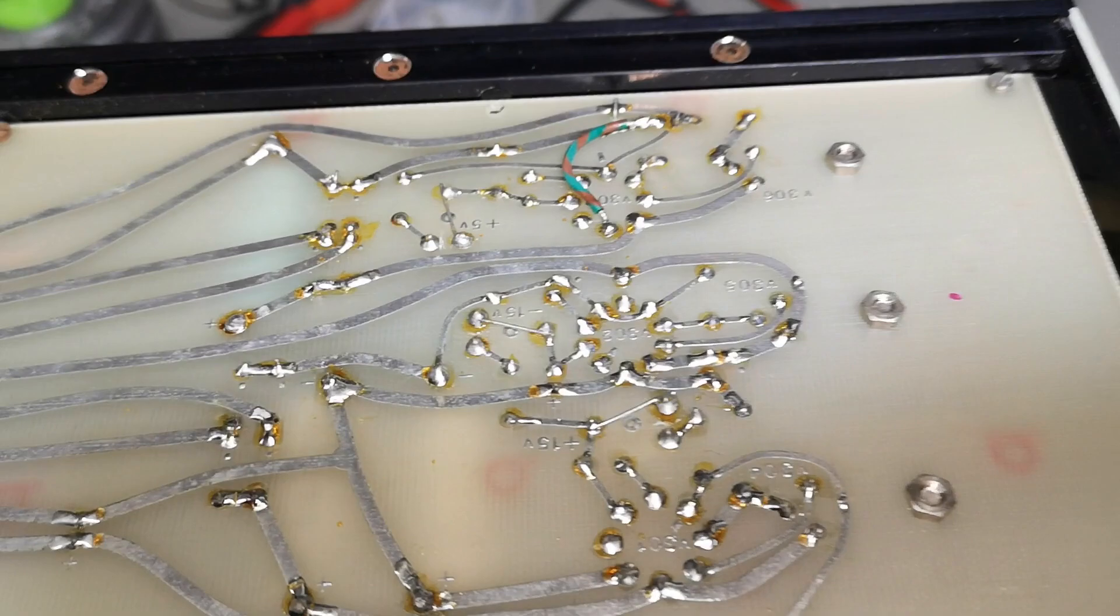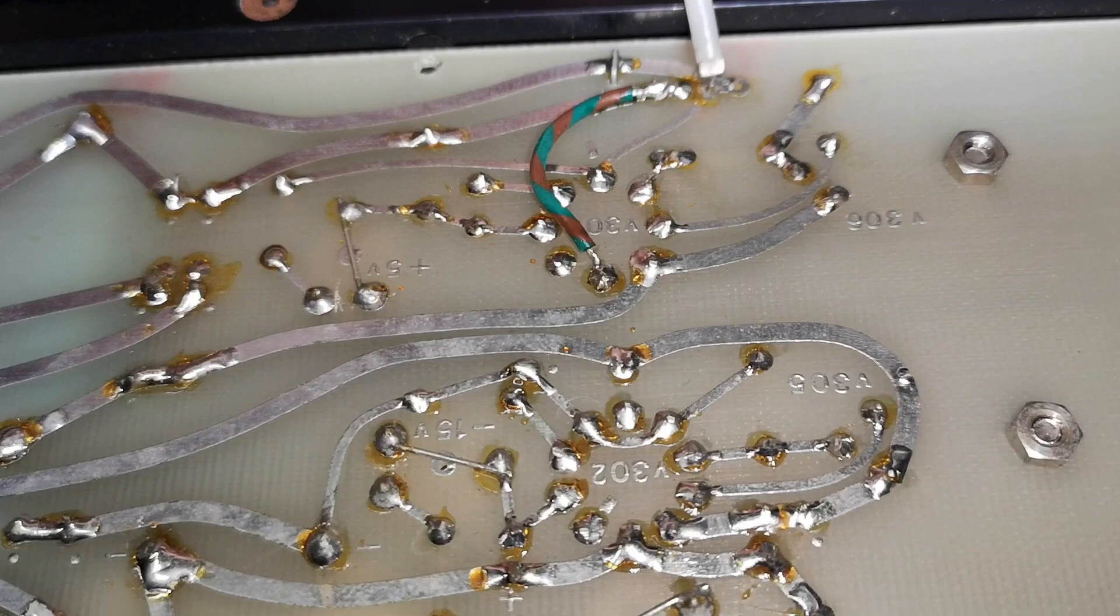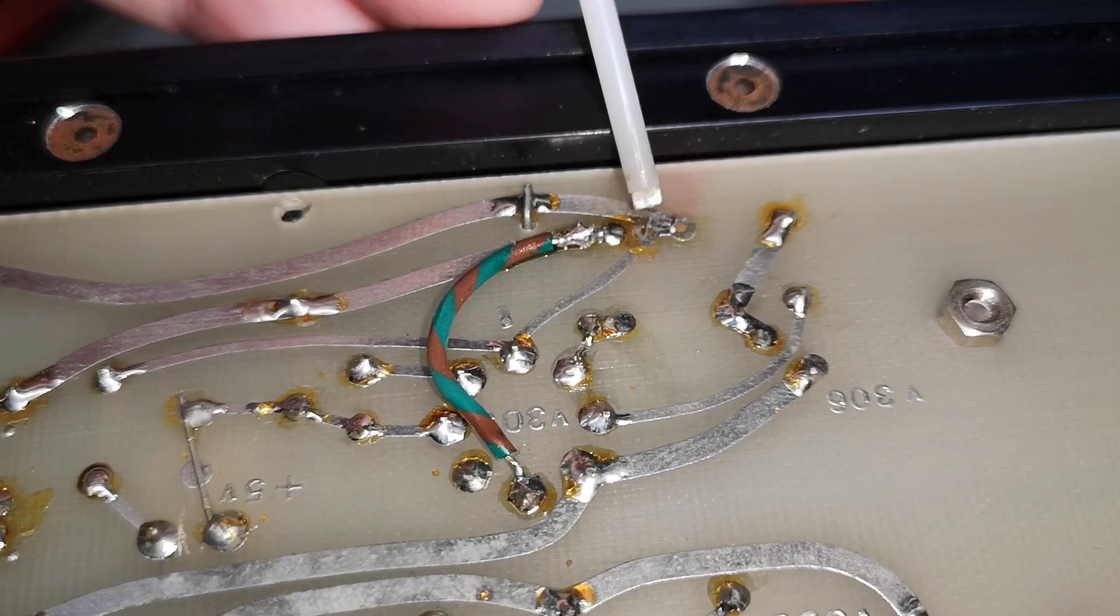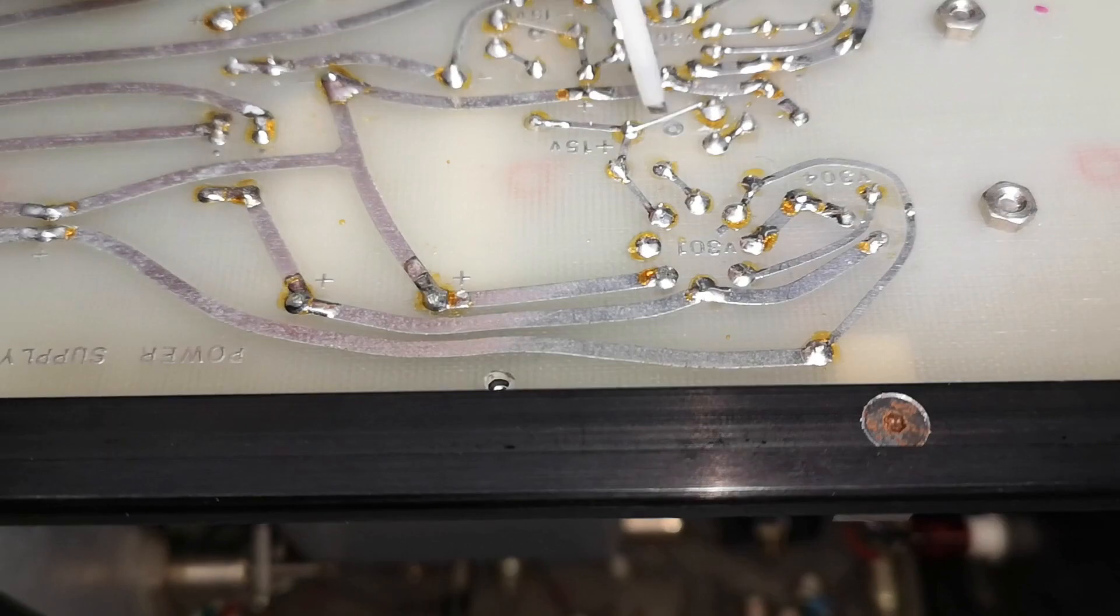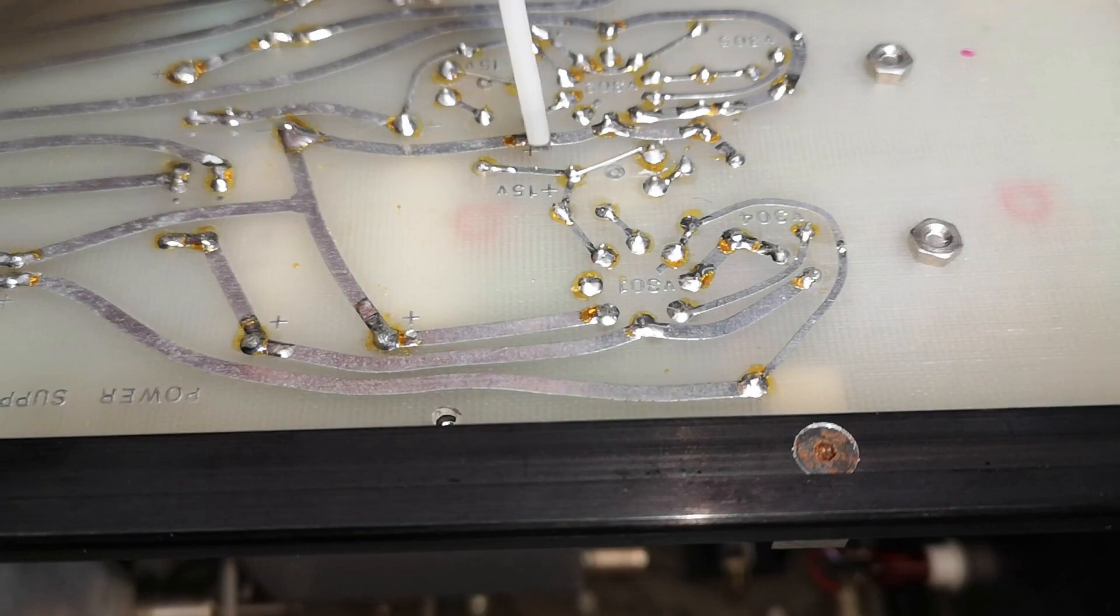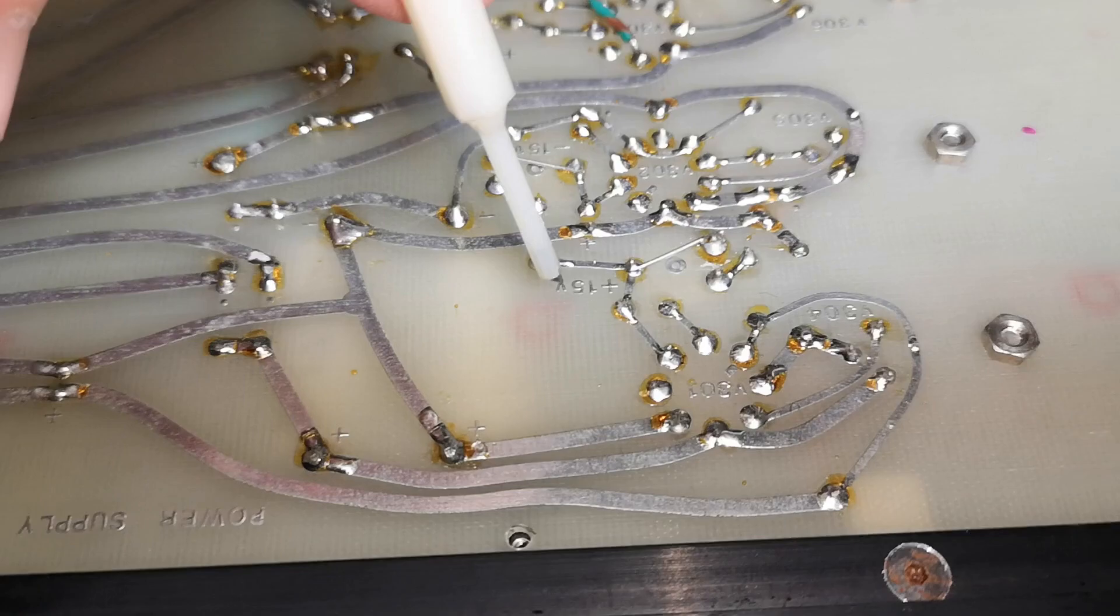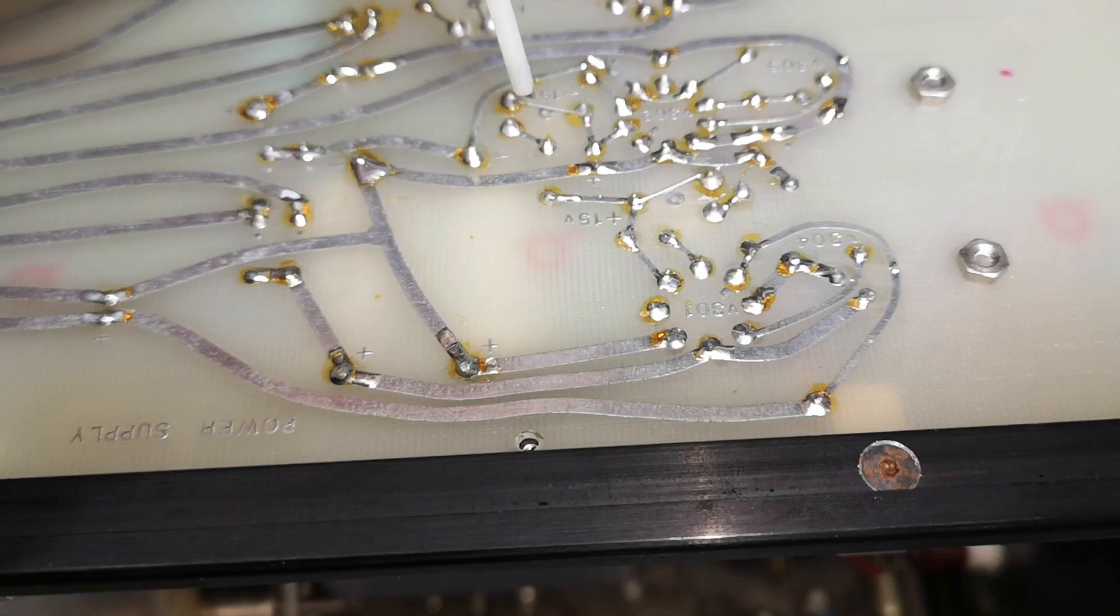This is the power supply. I don't know what you call this, not the best kind of soldering, huh? But this is probably somebody's been modifying the different voltages. I don't know exactly why they've been doing this. I trimmed the voltages a little bit down. It says plus minus fifteen and it was adjusted to seventeen. So I trimmed this as low as I could and that is like 16.2. So I guess some of those modifications has something to do with the voltages.